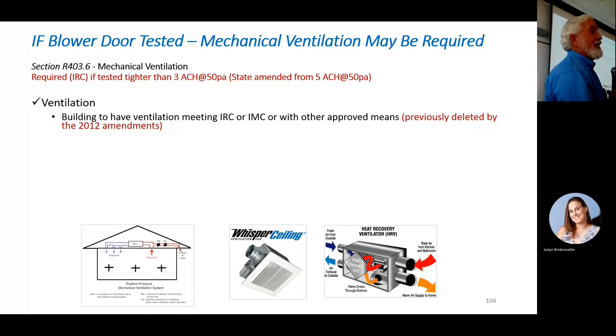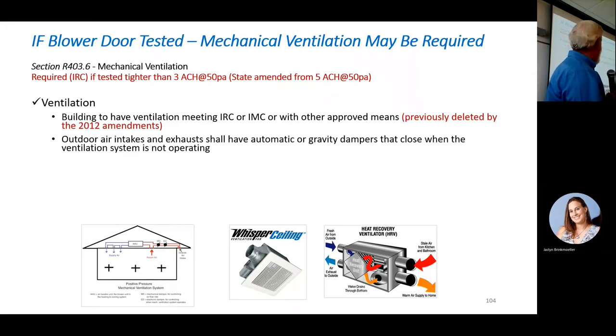This is what we call a balanced ventilation. That's the ideal because we know exactly how much we're sucking out and exactly how much we're putting back in, and we have a more balanced system. The only problem is they're a little bit pricey, especially with ducting and everything. But it's a good system. Whatever the case, if you have any of these or any other fans, the energy code requires that you have dampers that close if the system is not in operation. Just like your dryer vent or your bath fan or your kitchen fan, you have to have a damper that closes when it's not in operation. Why? And it has to be at your air barrier, at your thermal envelope. We can't rely on just the damper in the fan.